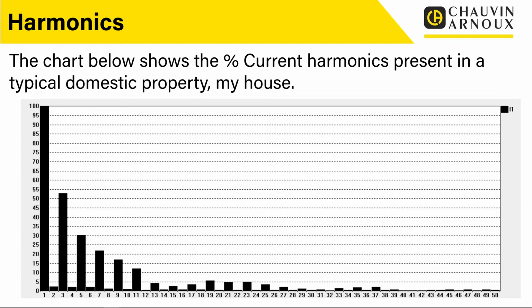So what you can see here is the percentage current harmonics. If you look at number 1 there, the first column, that's the fundamental. That's 50 hertz, and that's obviously 100% because it's based on the size of the fundamental. But what's interesting is when we get to the third harmonic, which remember is 150 hertz, we've still got over 50% of the current that we had in the fundamental. And then if we go to the fifth harmonic, again, we're at about 30%.